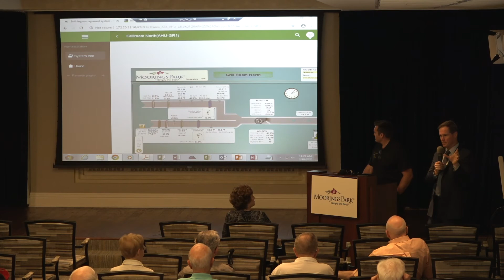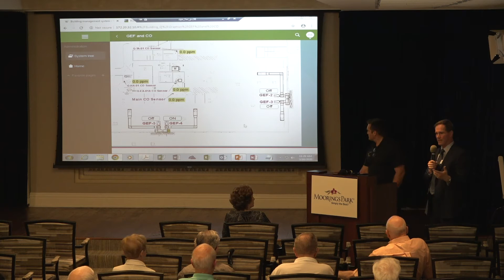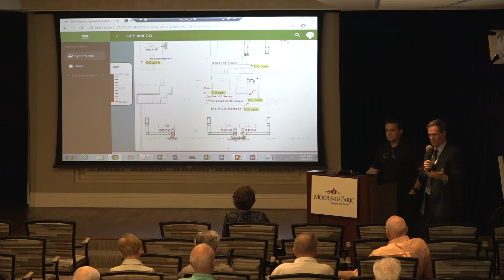I'm not aware of any air quality thing... I don't know if you can go to some of the garages, is there CO2 monitors in the garage? So there are automatic fans in all the garages. Well, I shouldn't say all, because some of the more open garages, like A and G Tower, don't need them because they're so open. But based on code, if there's a requirement for a fan, they'll be tied to a CO sensor. So if cars are idling in there, these fans will kick on to get us back to the right ppm, parts per million, of CO.